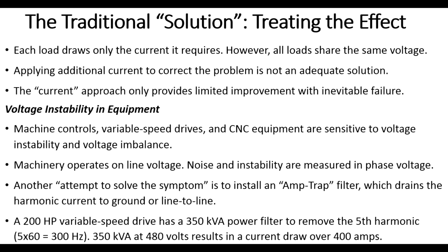Voltage, as I've said, is common to all of the loads, and in industrial factories, a lot of sensitive equipment, the controls in the machines, the motor drives, the positioning devices or positioning drives in complicated numerically controlled equipment, they do not like the voltage instability and voltage imbalance and harmonics and other electrical noise that they're inflicted with, though they are, for the most part, the cause of this noise.